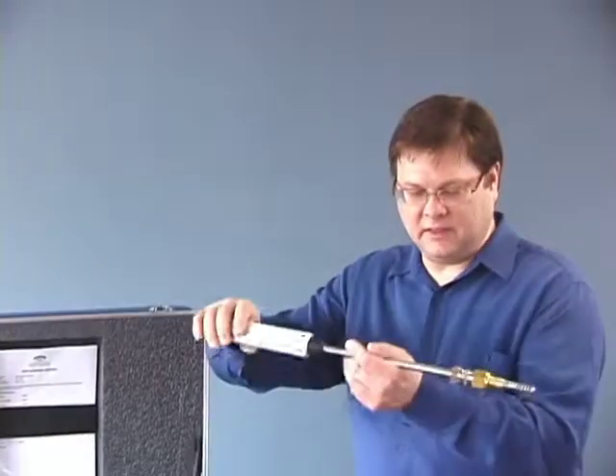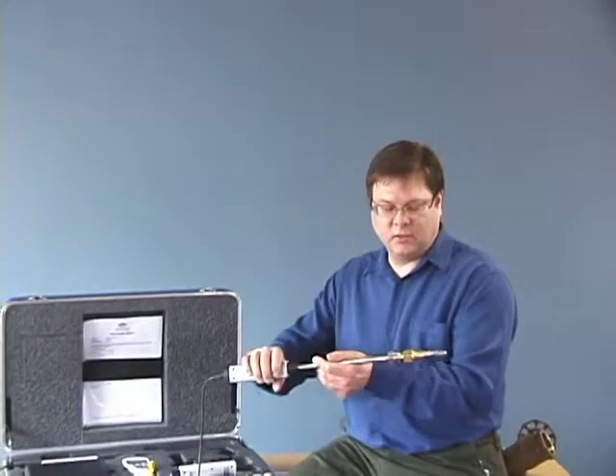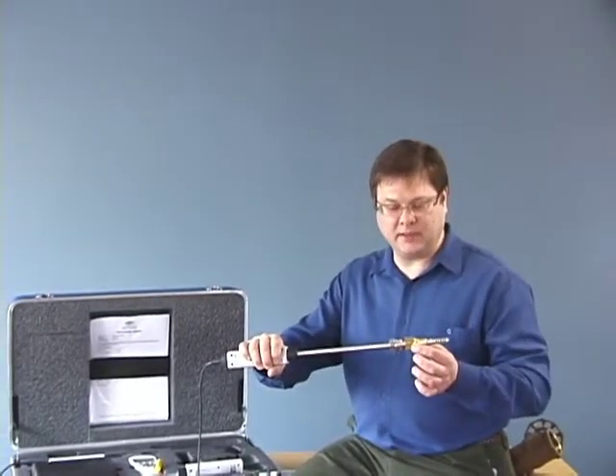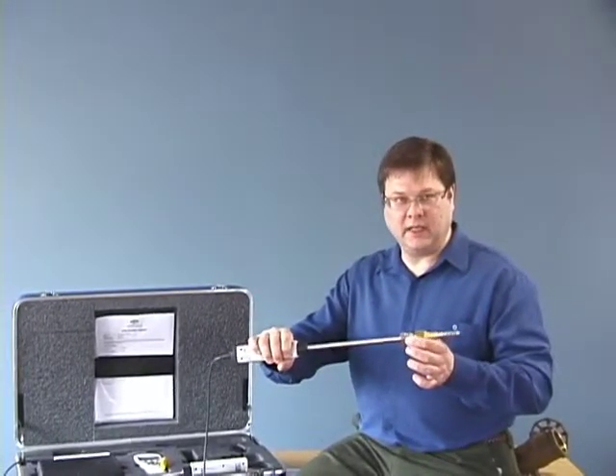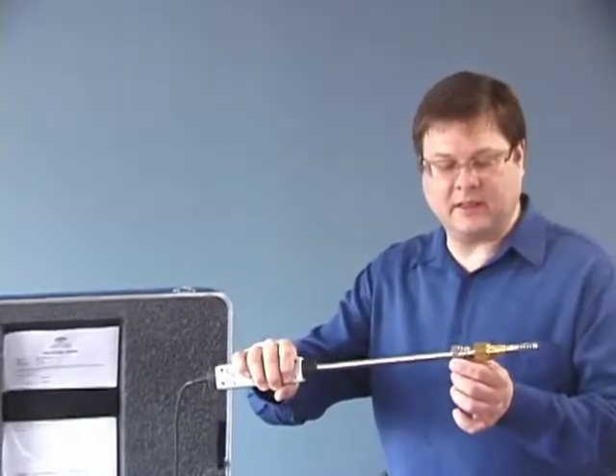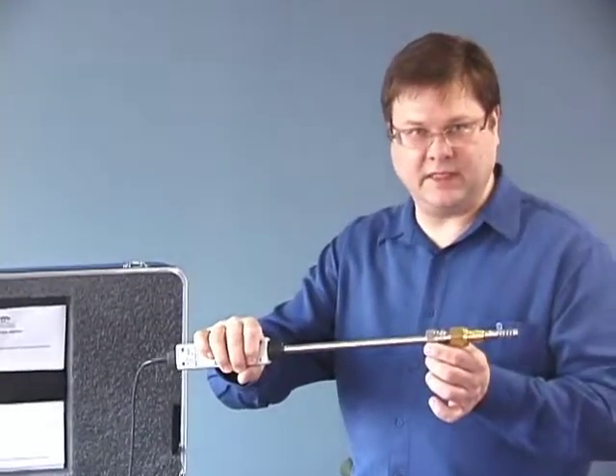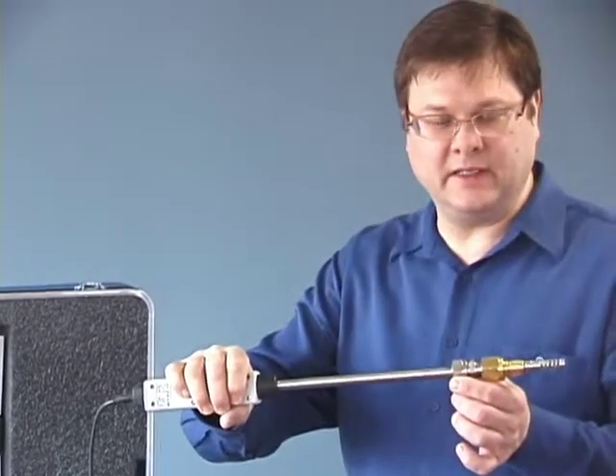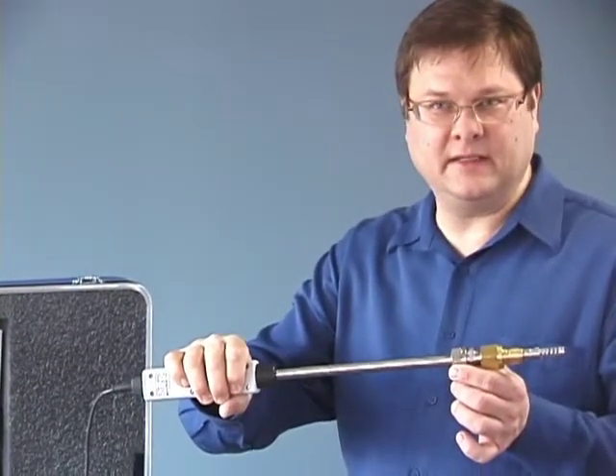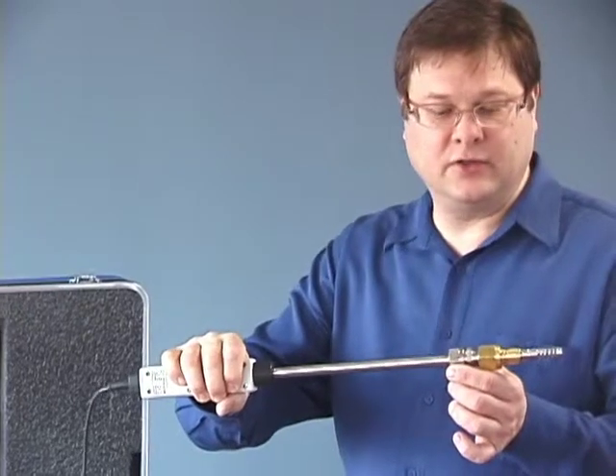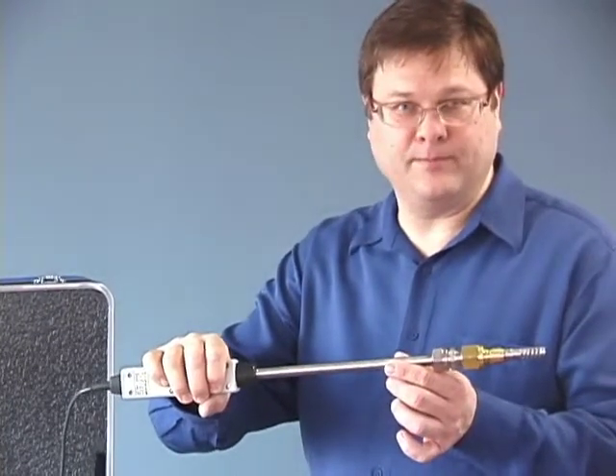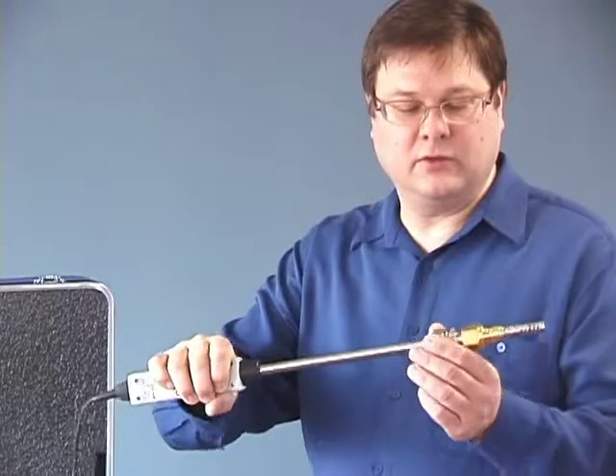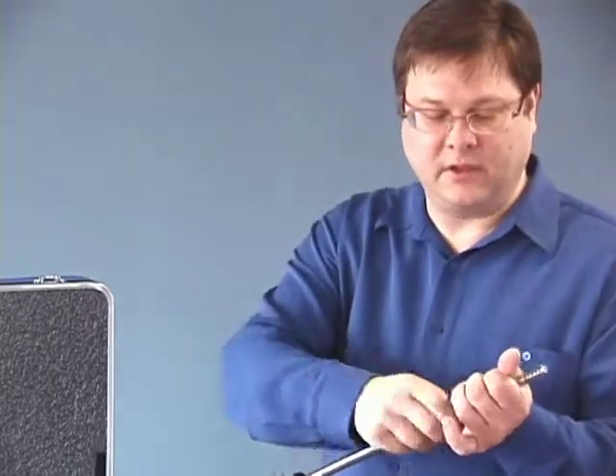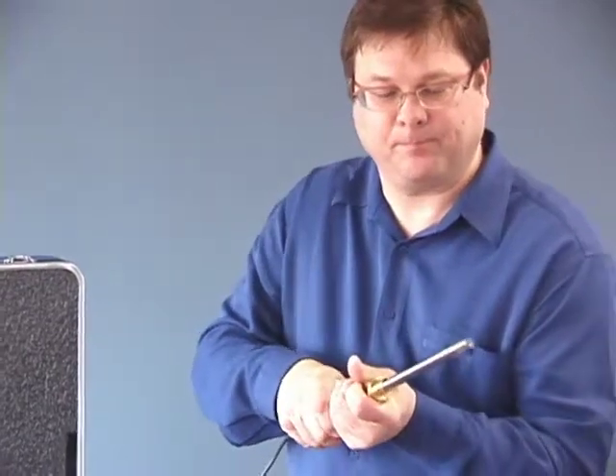The other thing we want to look at is the configuration of the plumbing assembly. We have what we call a quick connect plug, a fitting body, and a clasp nut. Now the clasp nut is not a compression fitting. It is actually an O-ring fitting that you only hand tighten and then tighten a quarter turn so that you don't score the probe. In this way, you can adjust the depth of the probe to any level that you want. Okay?